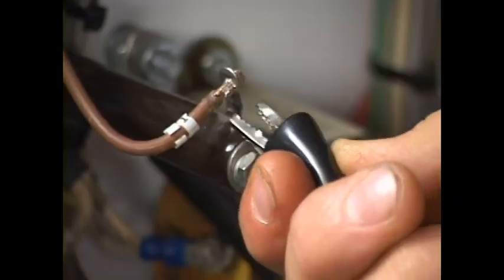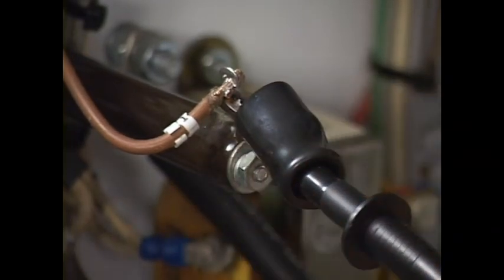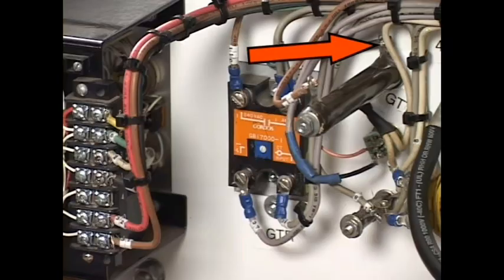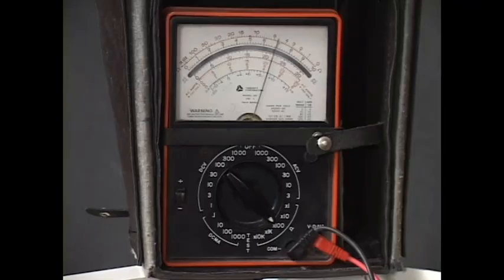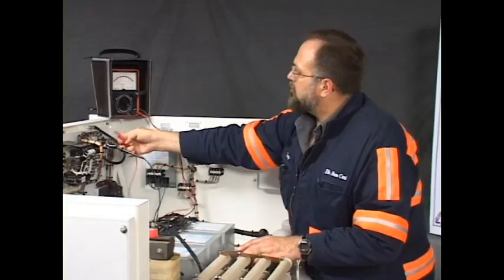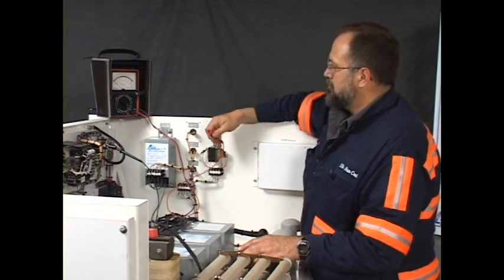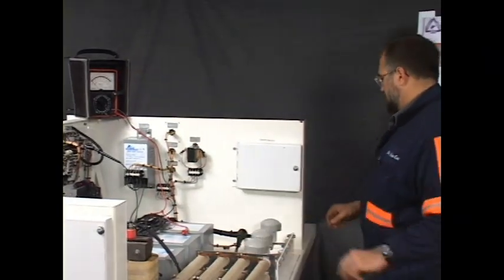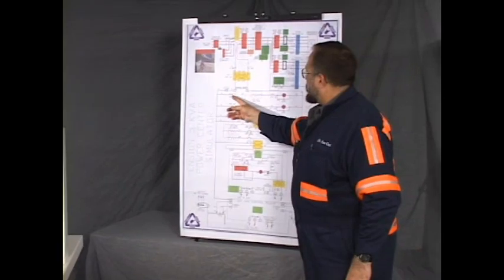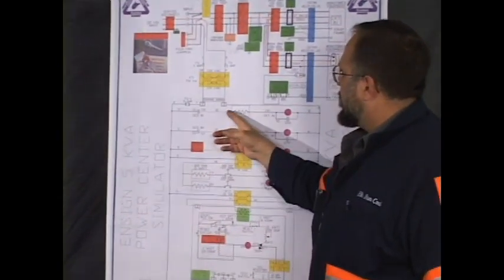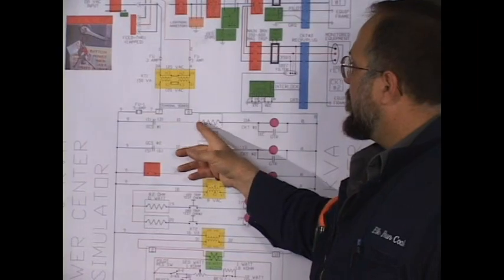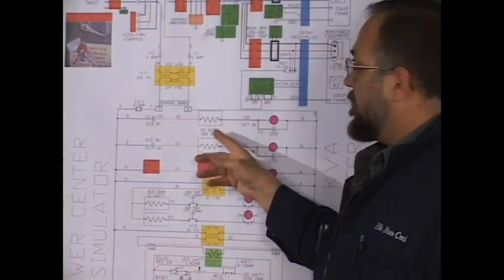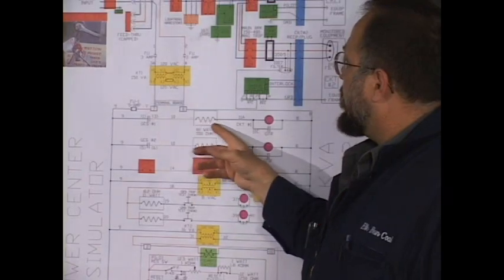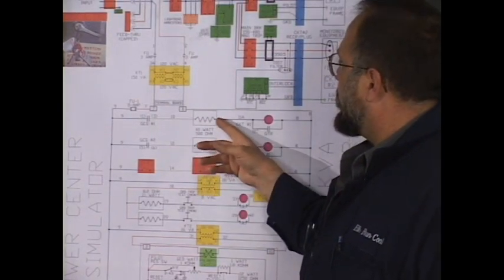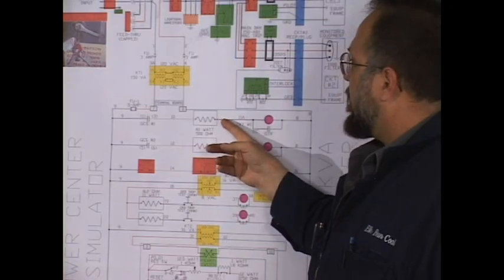Okay. I'm going to attach one probe to one side of the 500 ohm resistor and read the other side. As you can see, it reads almost exactly 5. 5 times 100, 500 ohms. So that tells us we've checked from GCS1 to the line side of this resistor, and the wire has good continuity. And then we've checked the resistor itself, and it's reading in the approved range and value for this device, 500 ohms.